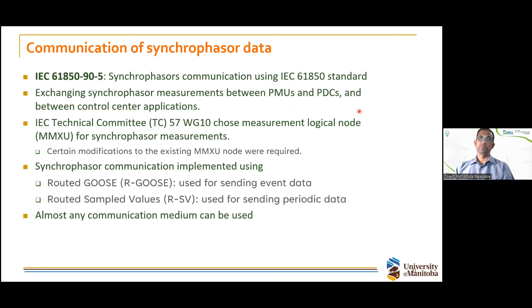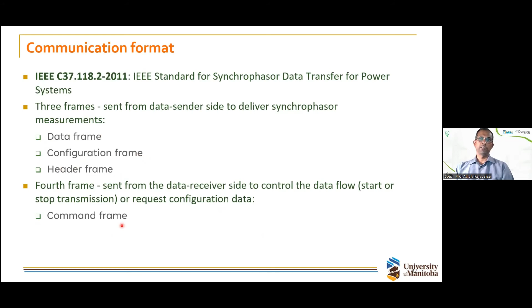The data can be communicated using what they call routed GOOSE, or routed sample value protocols defined in the latest version of this standard. In terms of how this communication happens, there are several types of data frames: one is actual measurement data, another is the configuration frame, another is called the header frame, and there is also a command frame. All of these are needed to do proper communication, and it's actually quite simple.